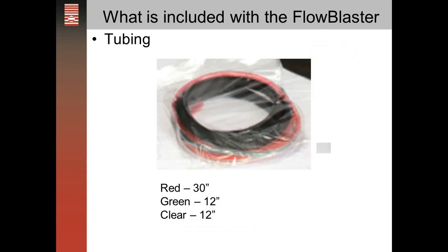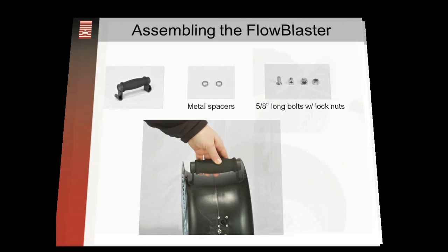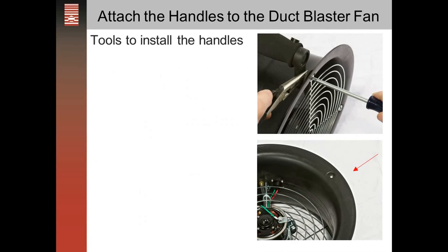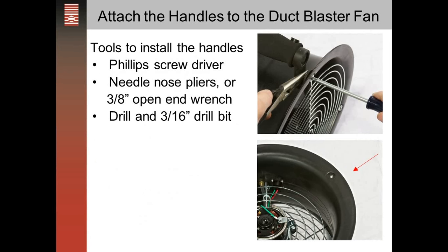The tubing needed for testing is included, as well as the two handles that you'll attach to the duct blaster fan. The tools needed to install the handles are a Phillips screwdriver, needle nose pliers or an open end wrench, and a drill with a 3/16 inch bit. The handle installs at the same location as the grate. On the opposite side of the grate there's a flat spot where you'll drill a hole in the center to install the two handles.